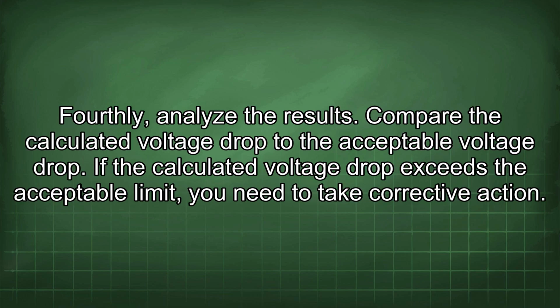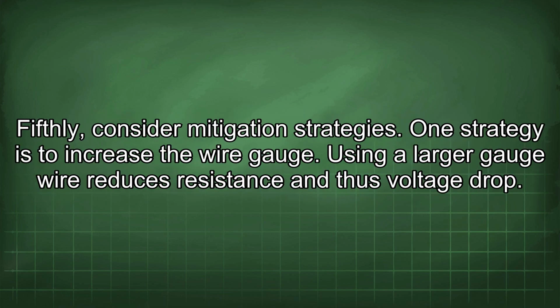Fourthly, analyze the results. Compare the calculated voltage drop to the acceptable voltage drop. If the calculated voltage drop exceeds the acceptable limit, you need to take corrective action. Fifthly, consider mitigation strategies. One strategy is to increase the wire gauge. Using a larger gauge wire reduces resistance and thus voltage drop.